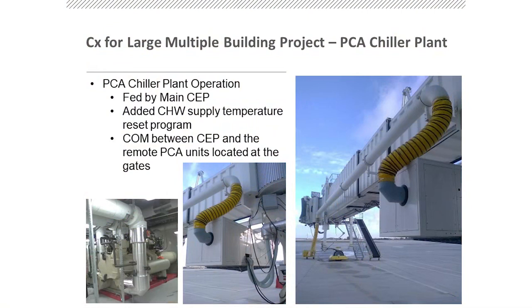As mentioned before, the PCA chiller plant has two sides to it. What you're seeing depicted here is the PCA units themselves, which are at each bridge, and the round flex duct you see is connected to the plane to keep it cool when it's in the gate between flights. And these units are served by, as we mentioned before, a low temperature glycol chilled water system and a satellite plant that's located in the airside terminal.